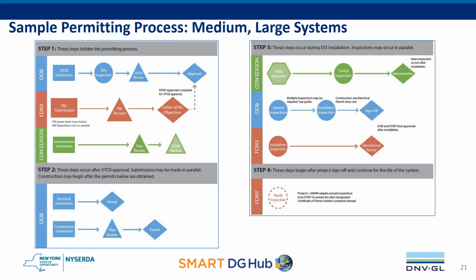Just as in the small system, however, this moves forward in the same way. First, submission of the application, review, discussion, perhaps some iteration to ensure that you meet the standards, and then eventually approval. Step 2 would be the construction and electrical permits. Step 3 would occur during or just after installation. And step 4, which is a new addition for the medium and large systems in comparison with the small systems, is that there would be a yearly inspection by FDNY to ensure continued compliance.